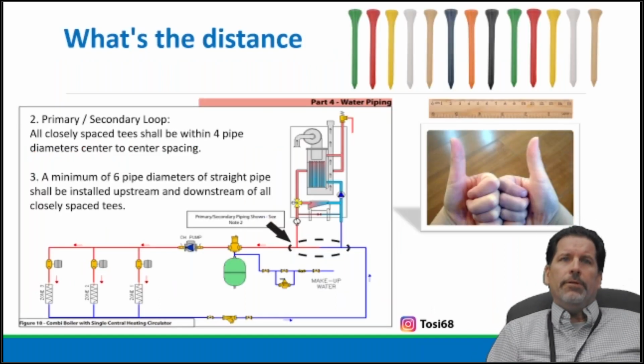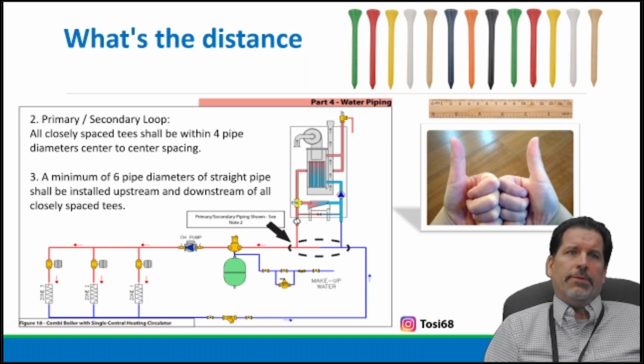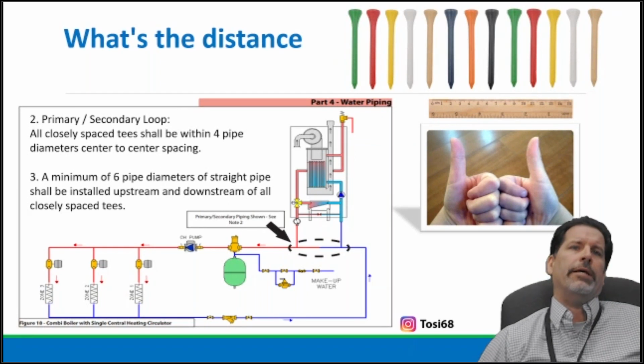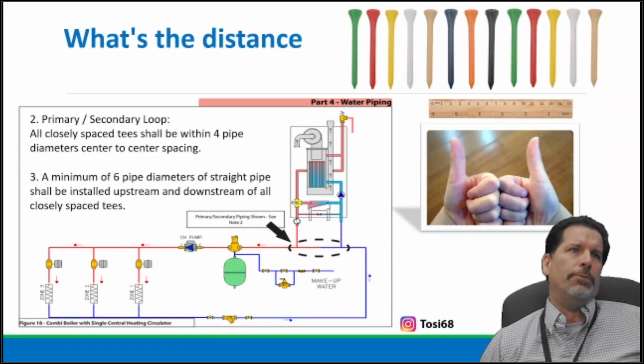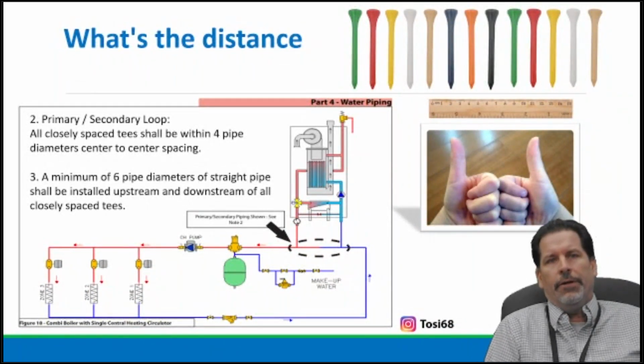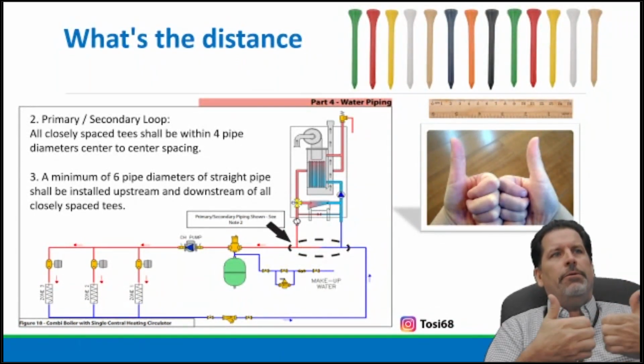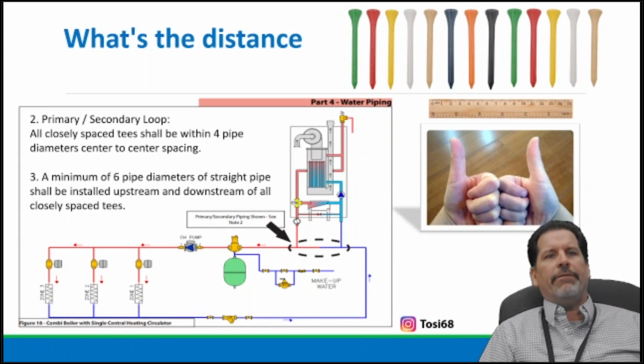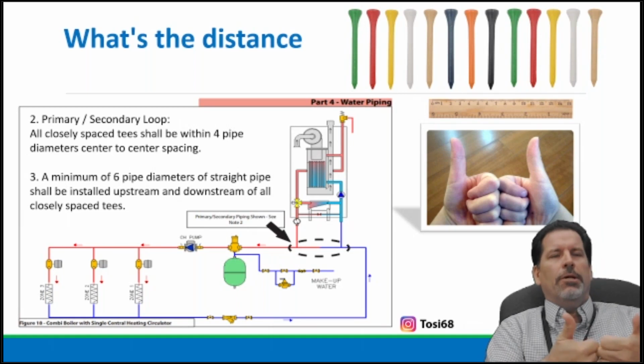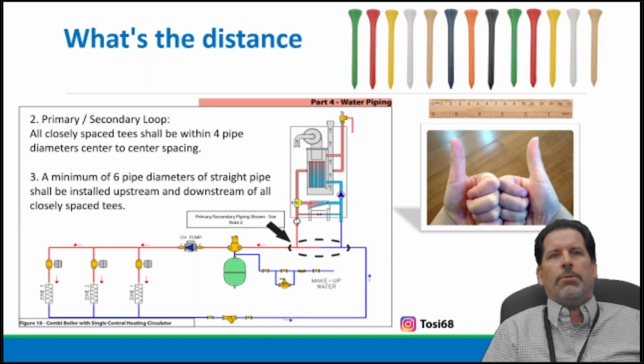What's the distance on closely spaced tees? This is typical, out of one of our manufacturers' installation instructions, talking about primary secondary loop. All closely spaced tees shall be within 4 pipe diameters center to center. That's what we're showing with the illustration of your knuckles, measure it, what is your measurement? If you put your knuckles together and take a look, mine was 6 inches, so I know if I walk into a job and something looks off, I put my thumbs up and say, why are you 10 inches apart? We're no longer seeing that decoupling.